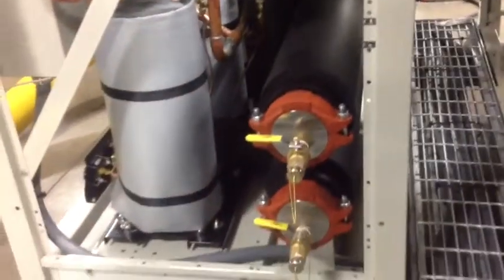As we pan to the left, you'll see the headers in the master module, and this stainless steel pipe in the upper portion of the frame follows all the way down the chiller outside and then connects to the rear module. This allows us to isolate the front modules from this rear module.